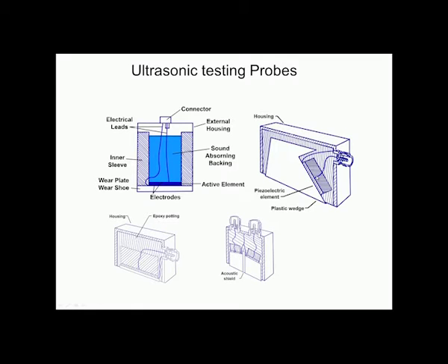Okay. So, this is how an angle probe is built. Here it is only one element, here also it is a single element, but in this case you could see there are two elements, and for these two elements there are two separate connectors and two separate leads. So, this is the dual element probe that I talked about some time back while talking about dead zone.